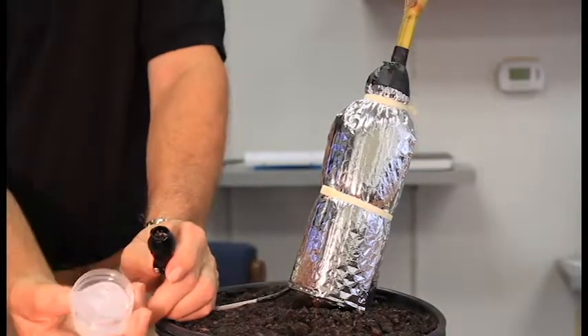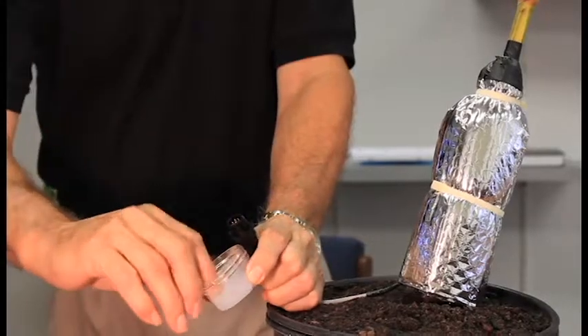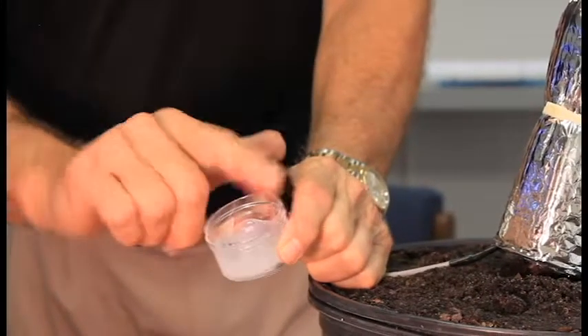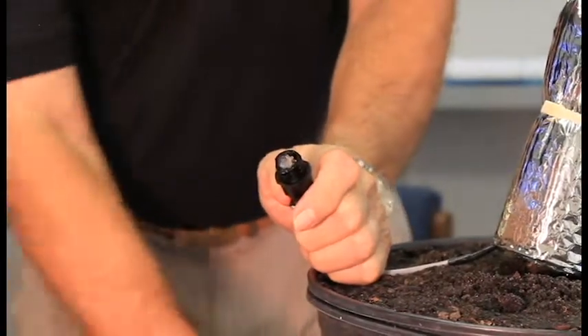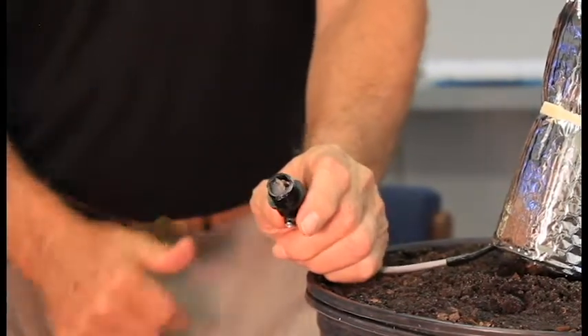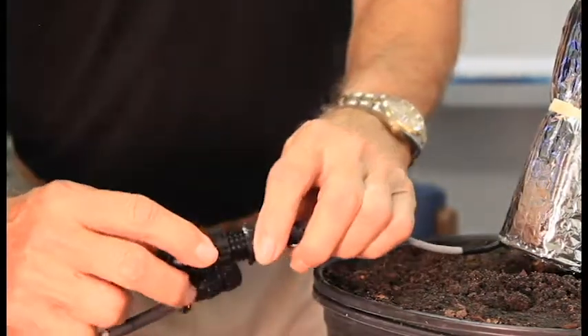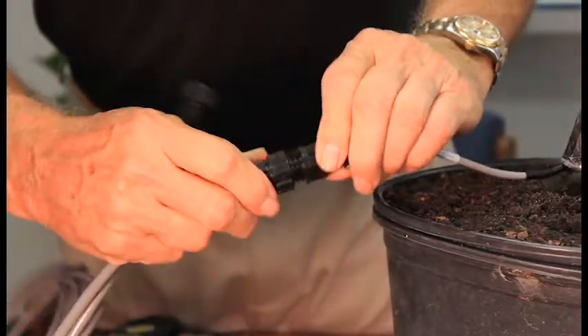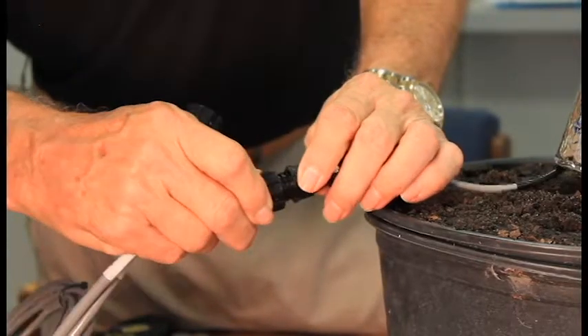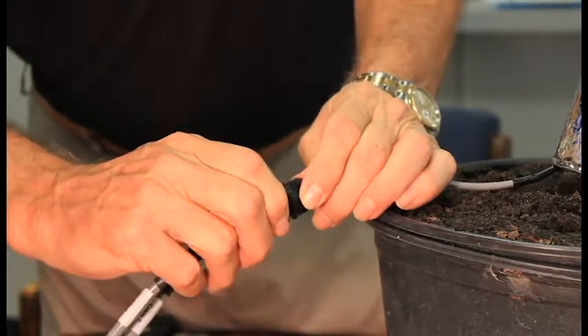I'll apply some G4 grease — this is a silicone insulating compound. I'll put about half a gram or so in there, and that will exclude any excess moisture that could condensate around the threading. Then I'll take the cable sensor, which is a locking sensor. I'll need to adjust it so that it first snaps into place, then I'll twist the locking connector and the whole thing will close, and finally you'll feel a snap.